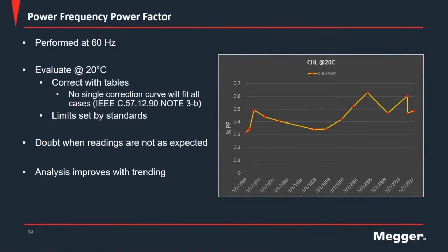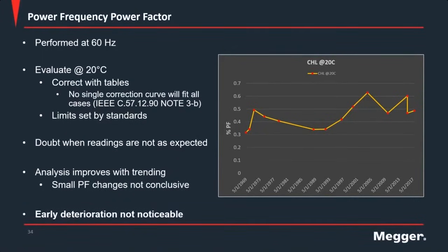So when we see this trending graph, it still doesn't answer a lot of questions for us. We can't say that the bouncing around that it's done at the end is really indicative of the bushing getting that much worse. And the main thing to note when we do power factor testing at 60 hertz is that early deterioration is not noticeable. The values will change very small from a good or an excellent to a good to an aged bushing. And it's really only with other methods can we start to see these bushings change before it would show up at 60 hertz, and more on that later.